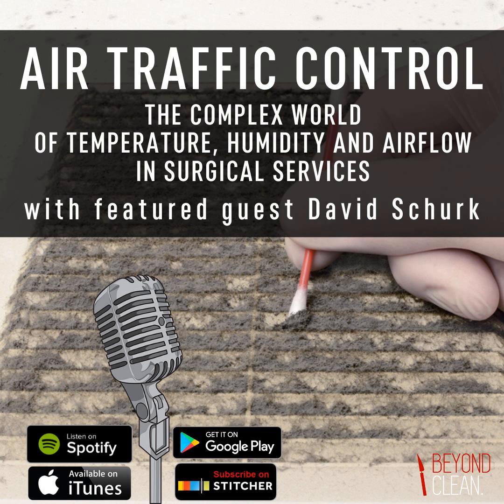All right, great. Well, from that perspective, there obviously are code compliance issues. ASHRAE, the American Society for Heating, Refrigeration, and Air Conditioning Engineers, has their Standard 170, which in the industry we consider to be the backbone of ventilation codes for hospitals in general. And then, of course, there is the Facility Guidelines Institute, or FGI, and they have their design and construction of hospital and outpatient facilities guidelines that hospitals and constructors have to follow as well. A part of that is ASHRAE Standard 170, which goes into detail with regards to things like temperatures and relative humidities, pressurizations, air changes, et cetera.